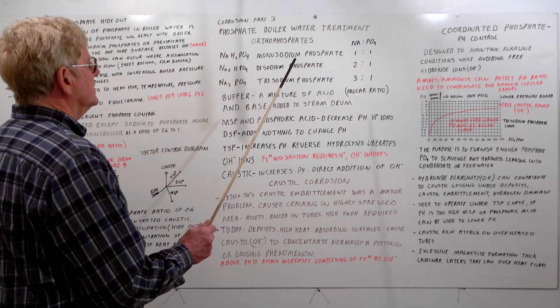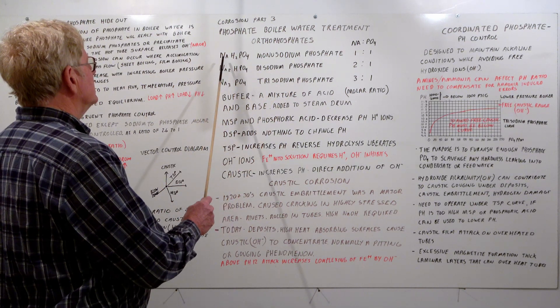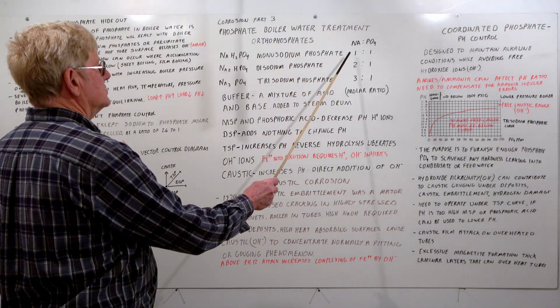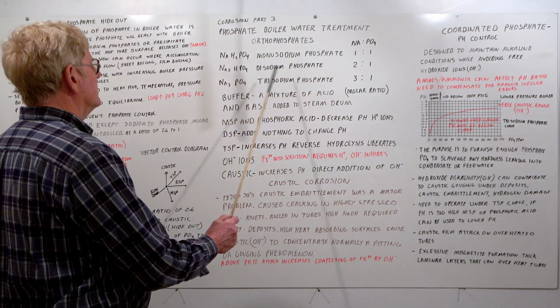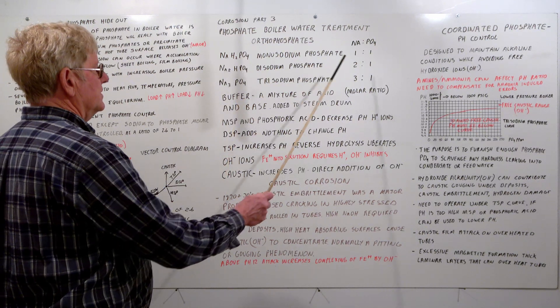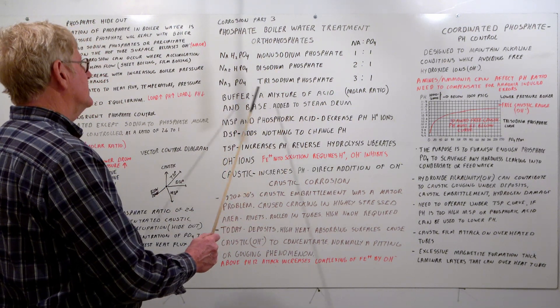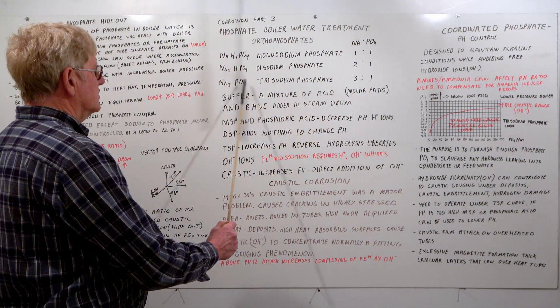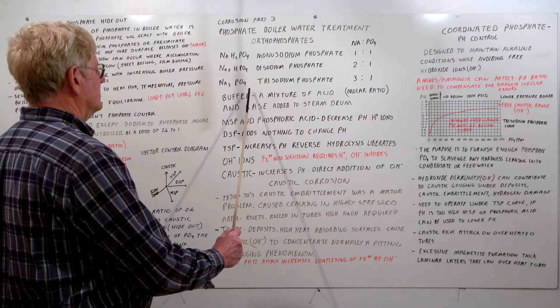We're dealing with orthophosphates. We have monosodium phosphate — one sodium, one phosphate, a one-to-one sodium-to-phosphate ratio. Disodium phosphate — two sodiums, one phosphate, a two-to-one ratio. And trisodium phosphate — three sodiums, one phosphate. Trisodium phosphate is what is predominantly used in boiler water treatment.